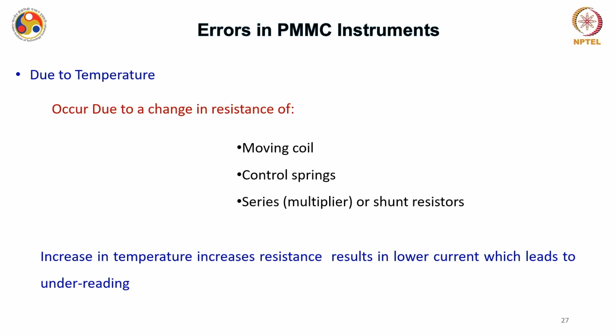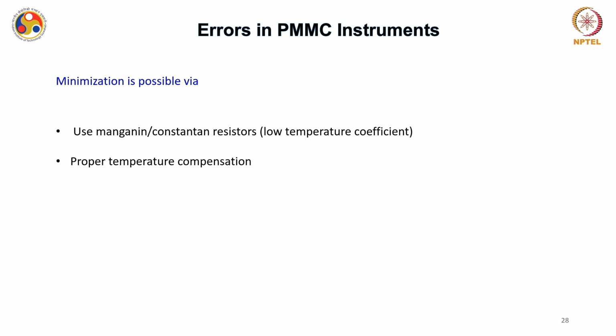Mostly these materials, like the coils, springs, or shunt resistors, are metallic in nature and have a positive temperature coefficient, meaning increase in temperature increases resistance, resulting in lower current, which leads to under reading of the actual value. This can be minimized by using manganin or constantan resistors which have a low temperature coefficient, or by providing temperature compensation provisions in the instrument, which can at least minimize the error.